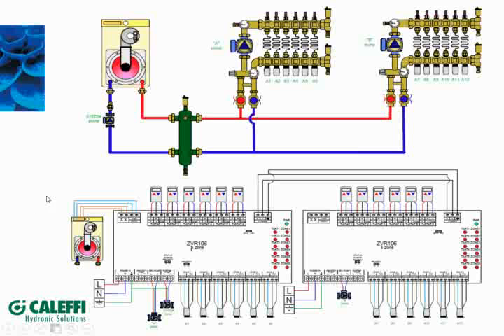It is possible to do, but let's say this was only a 3-zone box, right? And you purchased the extra transformer to have more juice. Yep. But keep in mind that the juice it takes to open those actuators is still going to flow through the thermostat. So the thermostat still needs to have some capability to control all of those. The key is really the thermostat. Can it handle that current draw when all 3 of those hit at once? It's not that we can't do it. And probably not, I would say, on a thermoelectric type of actuator that 3 of them could go. Well, I don't know. You have to read the spec on the thermostat.